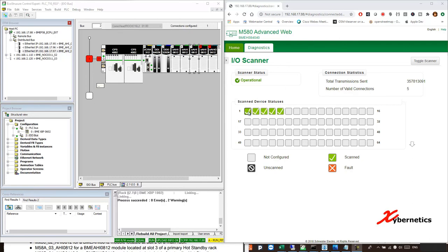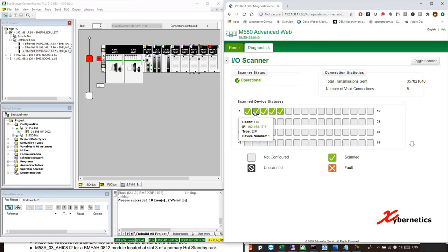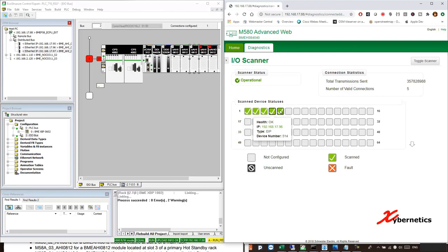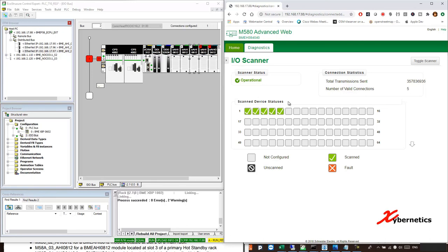So the way you detect that is that if you open your web browser here like that, you will see that your CPU, the CPU will say healthy and okay, but your CRA will take anywhere from five to two hours to become green, check green. It will show fault for five minutes to two hours and then come back on its own. That's a clear-cut indication that DHCP servers are fighting with each other. And another indication is that even when your CRA is checked and there's a cross here, you will not be able to ping any of this AI card. So that has to be taken into consideration.